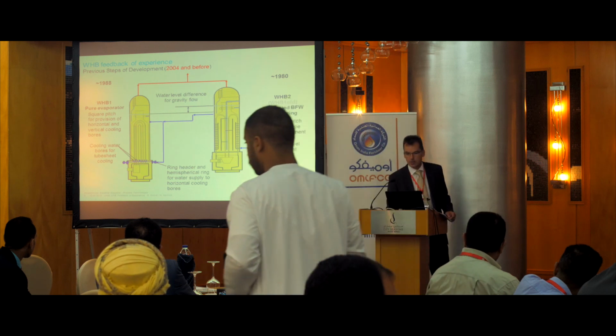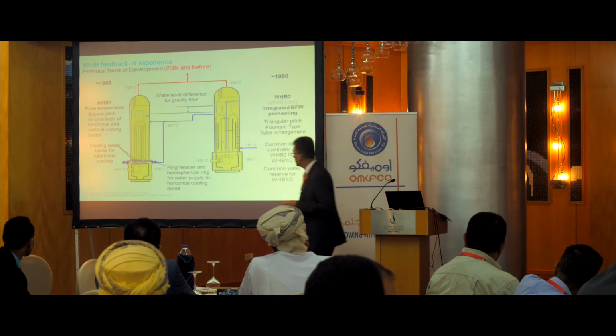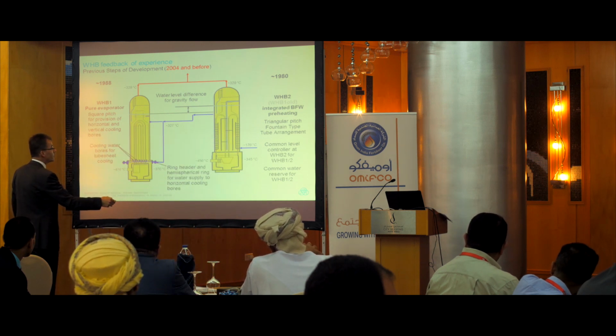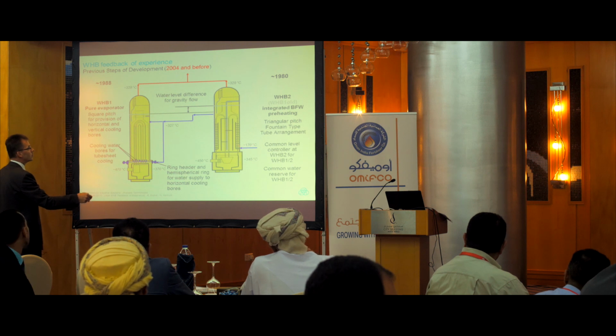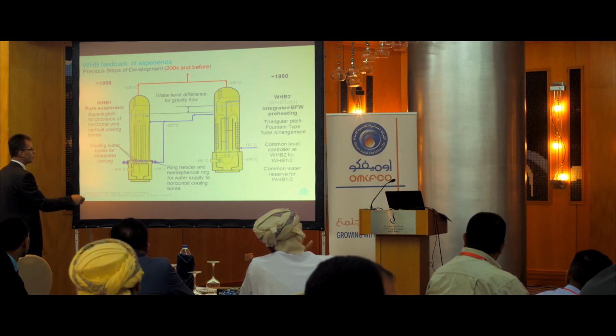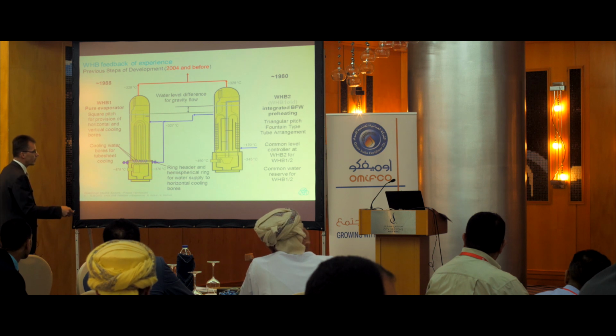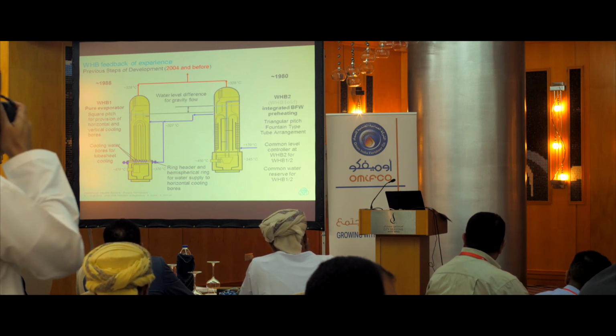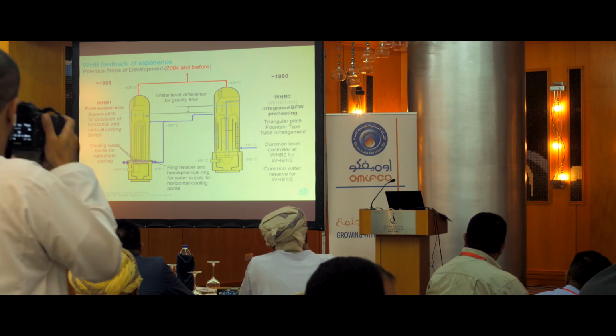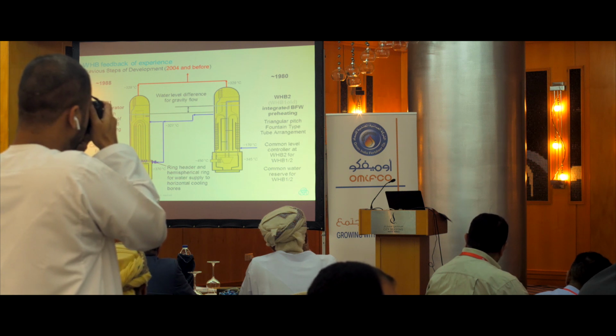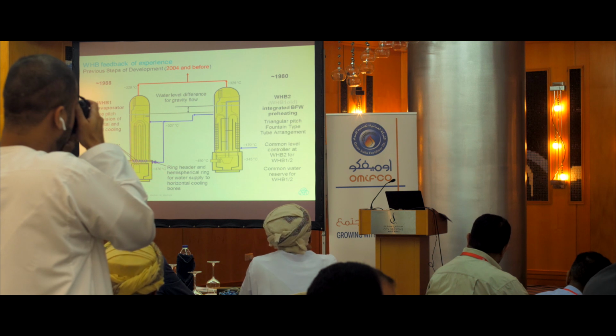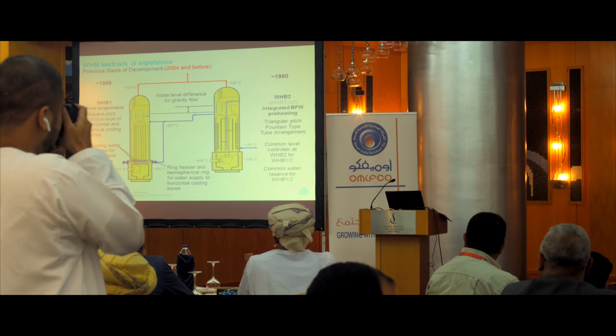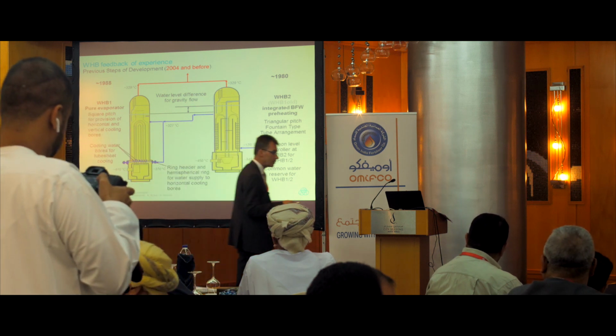I show you also some temperatures, typical ones, so that you get an impression. We normally go in with a two-converter concept and two waste heat boilers with about 170 degrees boiler feed water, steam production, saturated steam 329 degrees. This converter has 450 degrees incoming gas, going of course to the tubes, outlet about 345 degrees. Here we have nearly the same temperatures like the steam temperature, going in through the cooling bores. This waste heat boiler gets more hot gas, because this is from the first converter. It has about 470 degrees gas temperature, goes down to 370 degrees. We are even able to lower this to 300, 290 degrees nowadays. That means, of course, a bigger waste heat boiler.